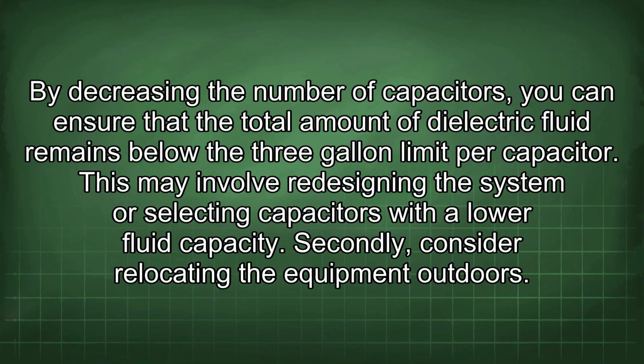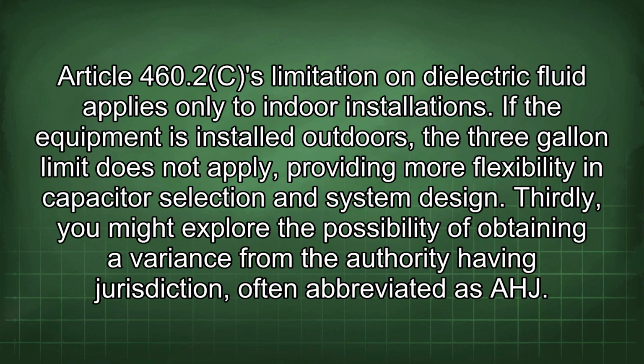Secondly, consider relocating the equipment outdoors. Article 460.2c's limitation on dielectric fluid applies only to indoor installations. If the equipment is installed outdoors, the 3-gallon limit does not apply, providing more flexibility in capacitor selection and system design. Thirdly, you might explore the possibility of obtaining a variance from the authority having jurisdiction, often abbreviated as AHJ.